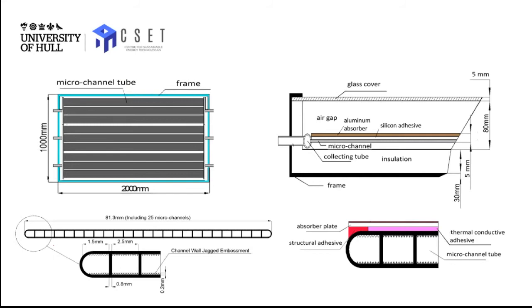So this is a panel. We have multiple inlets and outlets, with the panels connected from beginning to end, from beginning to end, making several U-turns, making the temperature uniformly distributed, preventing heat loss at the end channel, and as a result, we can achieve higher overall solar efficiency. So this is an 8-panel array established in the manufacturer's factory. We tested the performance on site and then delivered it to the UK to test the overall performance.